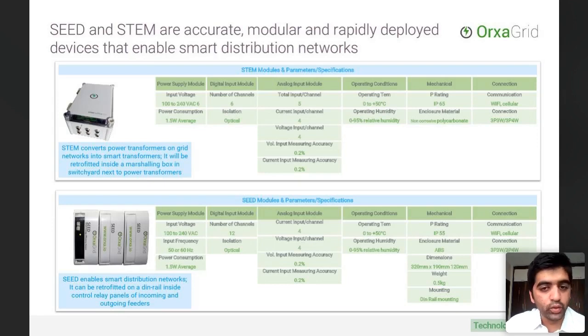Both the seed and stem do direct measurements of currents and voltages. That means if it's a substation, we can take the PT secondary, which would be 110 volt AC, directly into the device. On current measurement, we use either clamp-on CTs or Rogowski coils to directly monitor the current on the feeder or the transformer outgoing.